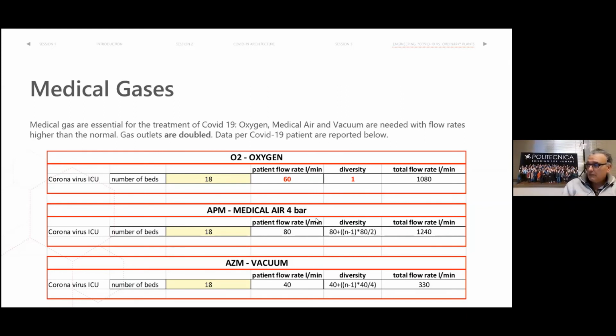All the outlets are doubled, so you have 2 outlets per patient for oxygen, for medical air, and for vacuum. Of course, for oxygen, there are 2 outlets of 30 liters per minute each. So the total is 60. They can use 2 if they need.